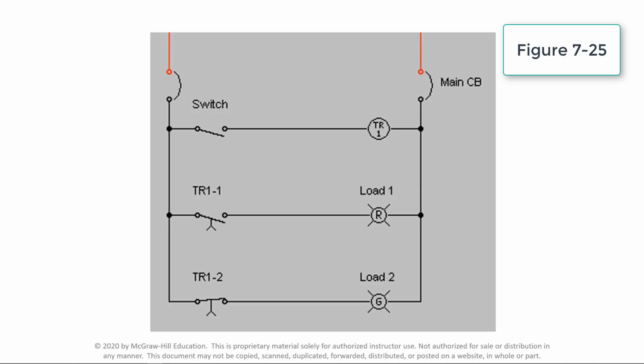This video demonstrates the operation of an on-delay relay timer circuit. When the switch is closed, power is applied to the timer coil, but the contacts are delayed from changing position. With the switch still closed after the 10-second timing period, the normally open contacts, TR1-1, close to energize load 1, and the normally closed contacts, TR1-2, open to de-energize load 2.